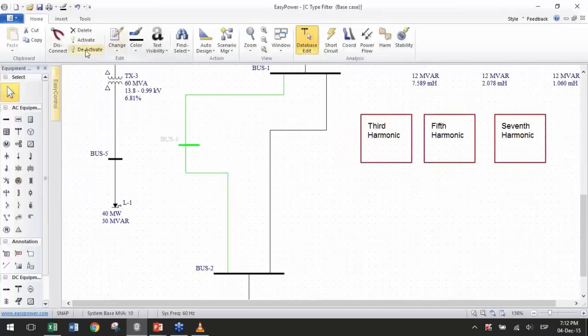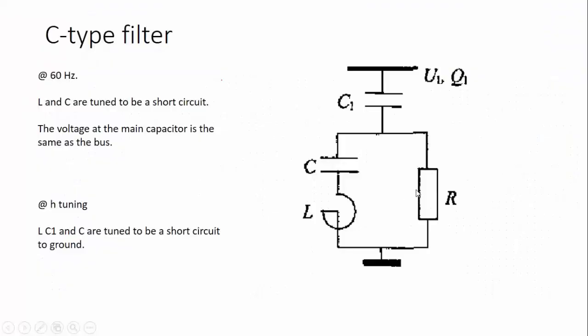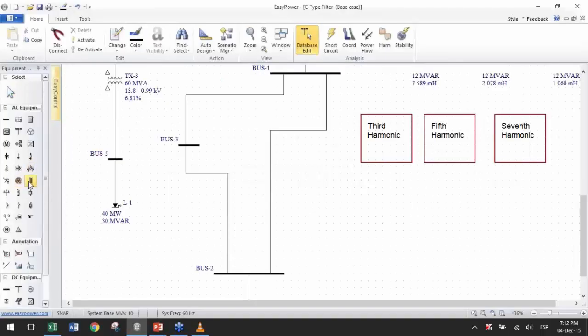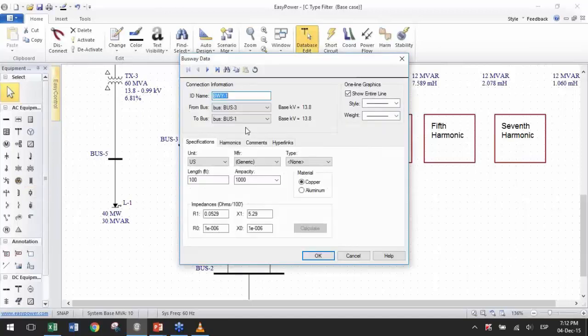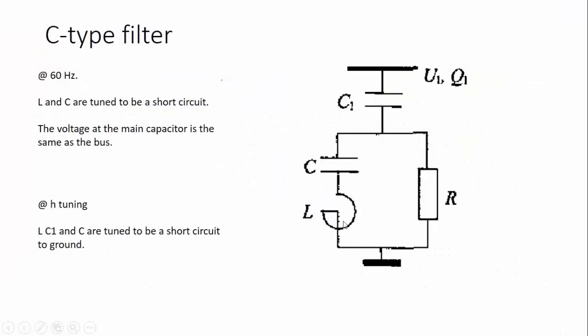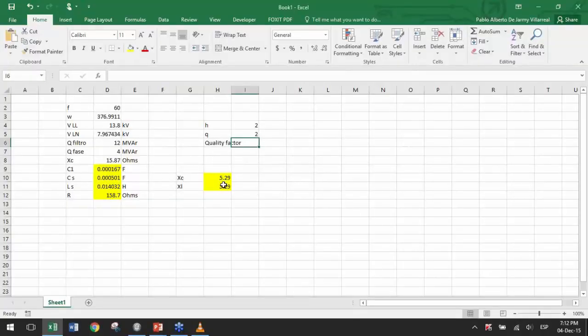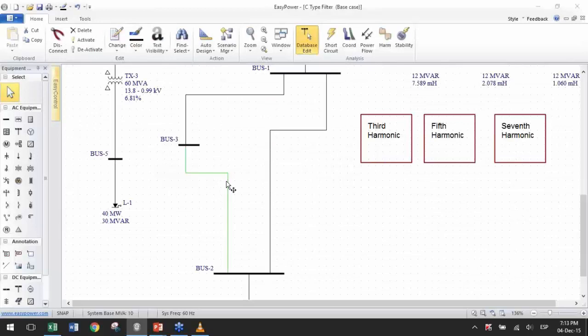Now, for creating the other elements of the C-type filter, which is the resistance, this capacitance, and this inductance, I'm going to use busway. And remember, this is a little bit of cheating, but it works. Now, busway allows me to enter impedance. Now, let's check it out. The inductive reactance, yes, this impedance, I got it from my Excel, and it's 5.29 ohms. Now, this is plus j. It's an imaginary part which is positive, as is any reactance. So I'm going to put that in here.